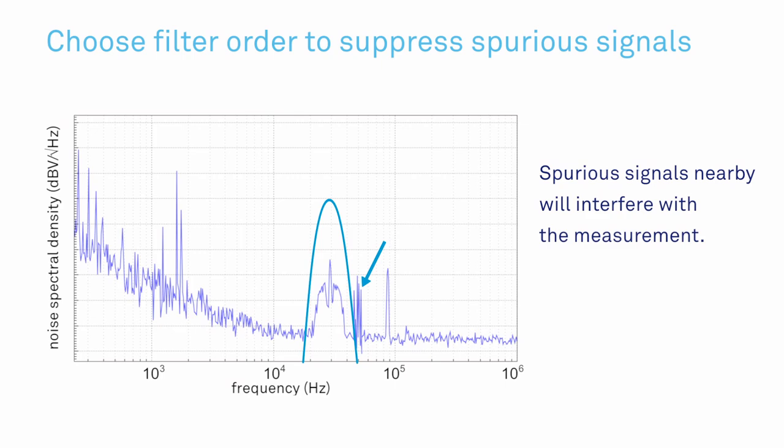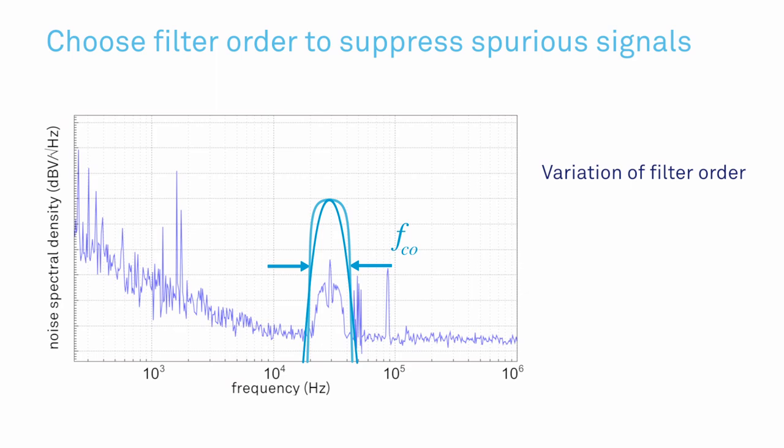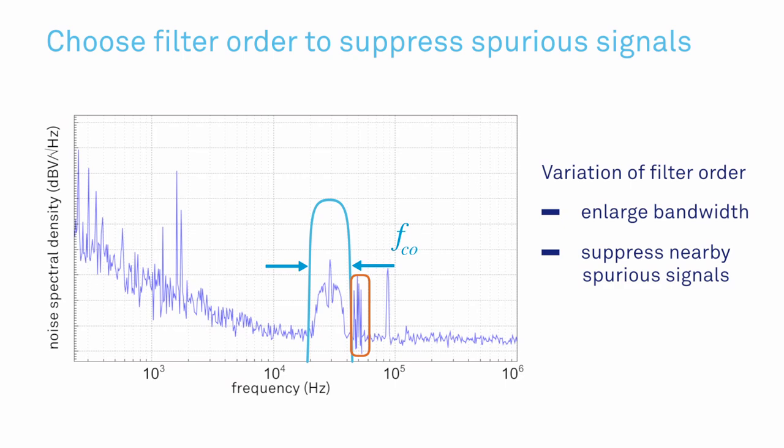In case there are spurious signals nearby, they will interfere with your measurement. The filter order adds a degree of freedom to the settings. With a higher order, a broader bandwidth can be selected while keeping the unwanted frequency suppressed.